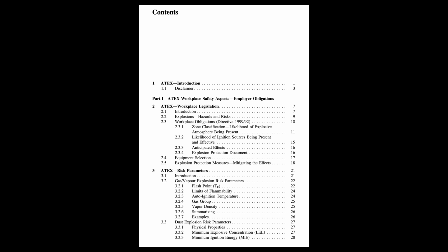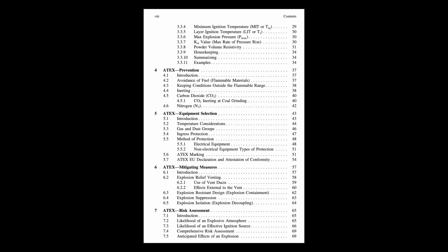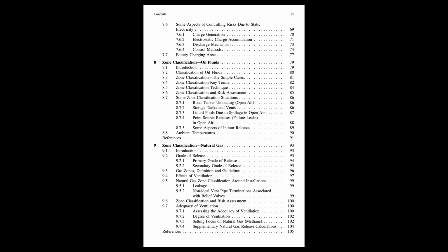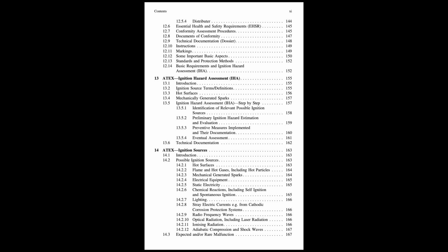And confined versus unconfined explosions. Unconfined explosions, like a gas cloud igniting outdoors, generally produce lower pressures unless there's significant turbulence, maybe from surrounding structures. Confined explosions inside equipment or buildings are usually much more damaging because the pressure can't easily dissipate. Even mixtures near the LEL or UEL can generate substantial pressure if ignited in a sealed vessel. So confinement really matters. Hugely. It dictates the potential pressure buildup and the effectiveness of measures like venting. So there's definitely more to an explosion than just a loud bang and a flash. Absolutely. Understanding that science really underpins why all these preventative and protective measures we've spent this time discussing are so incredibly vital.